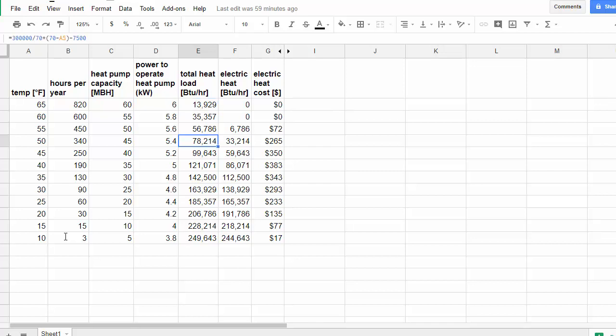So there's no cost associated with the first two rows because we don't need the electric heat. But there is cost associated with this row and every other row after. So that's a lot of computation. So I made a quick table to summarize these results and get us to an answer. So the first four columns here are the same as what's given in the problem. And now I've added this column E, which is for the total heat load. So that's the 300,000 design divided by 70, times the actual delta T for whichever one we're trying to figure out. And then this minus 7,500 is just to subtract those internal loads.